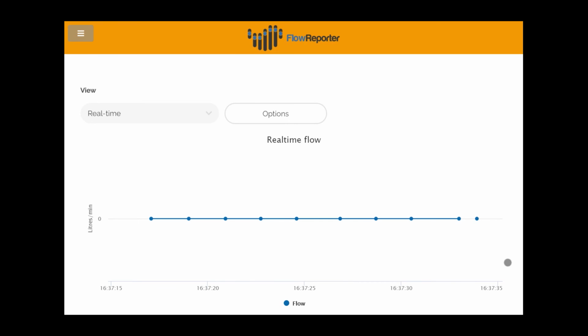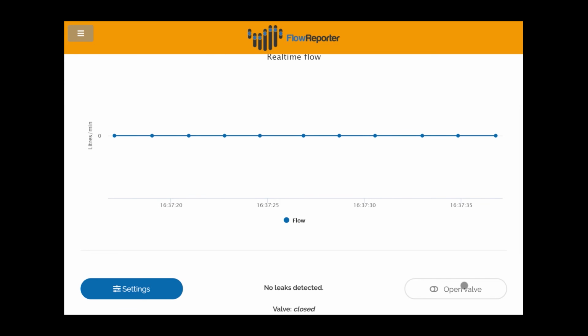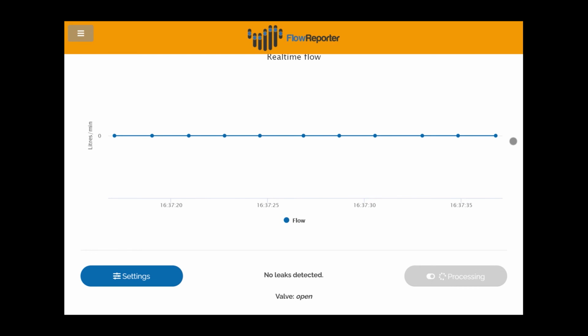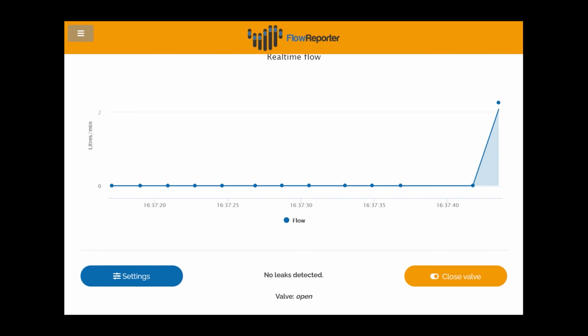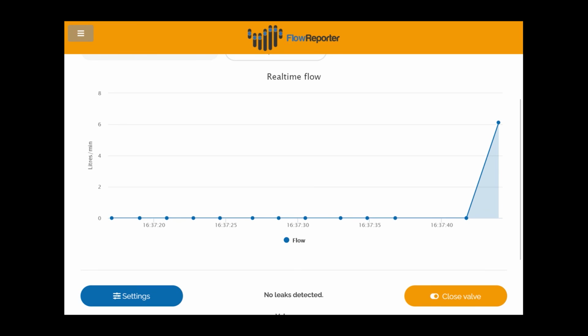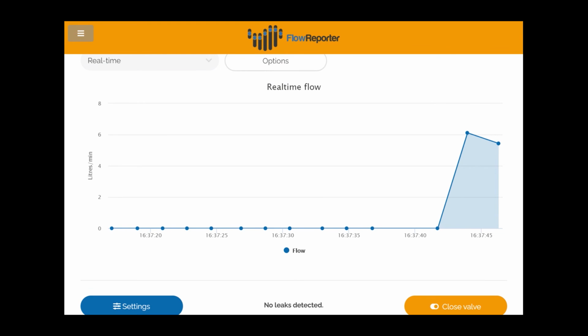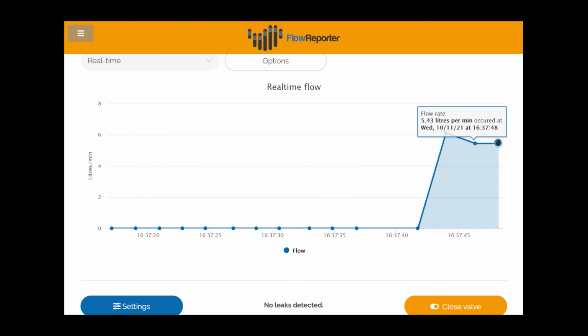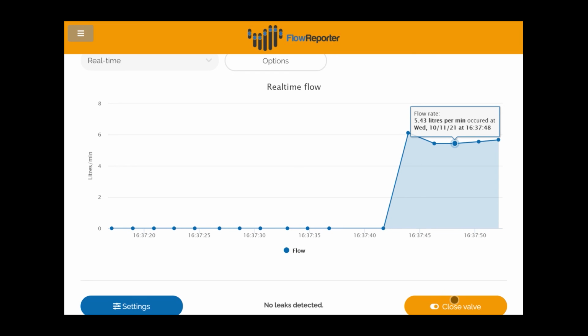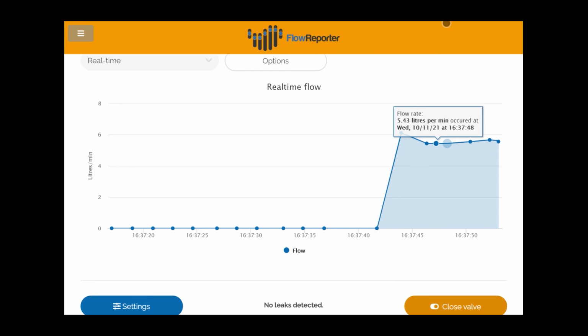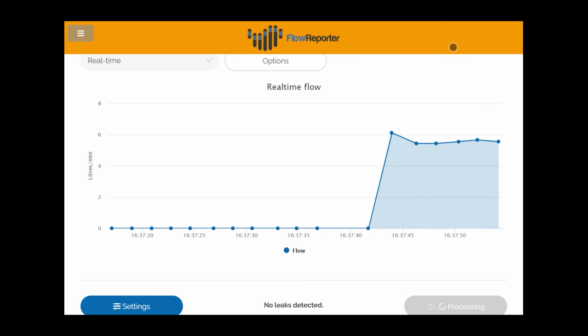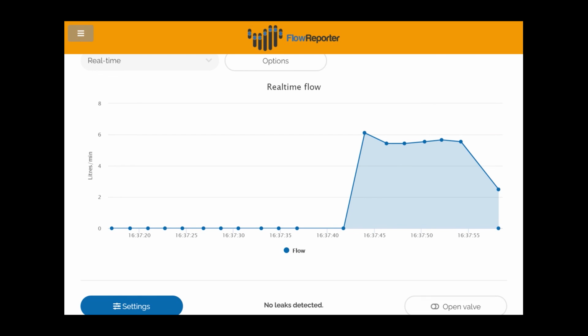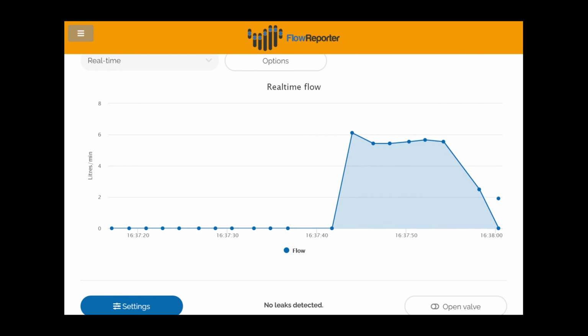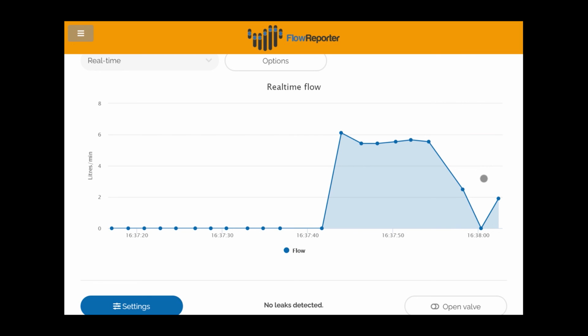At the moment we've got a tap open and the valve closed, so I'm just going to go down here and open the valve. First of all, we should see the tap turn on, and if the flow sensor is working correctly, we should see the flow rate increase. Then we'll close the valve just to confirm the valve works as it should, and also see the flow reduce to 0. So in this case, everything works fine.